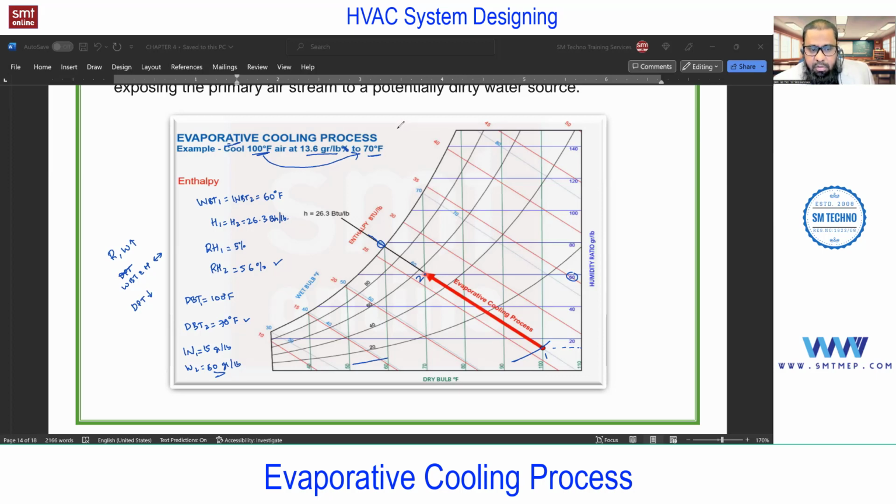For example, you cannot use this air cooler concept in Dubai, or in India, Vishakhapatnam, or in Al Khobar, or anywhere you have seashore areas. We cannot use this air cooler because in seashore areas, as the temperature increases, the humidity increases because of the availability of water and more and more evaporation in that area. If the moisture in the air is already at the maximum level, you cannot expect evaporation. No evaporation means no cooling.